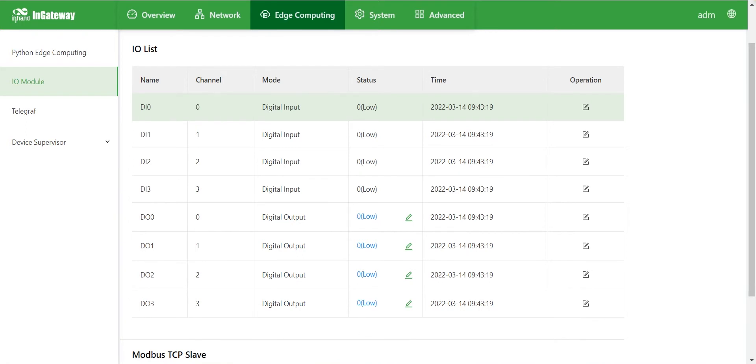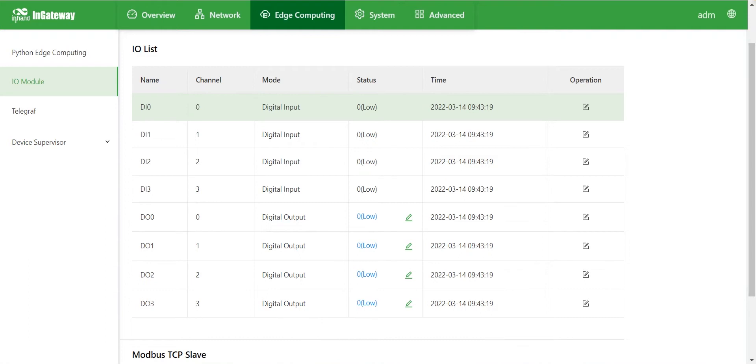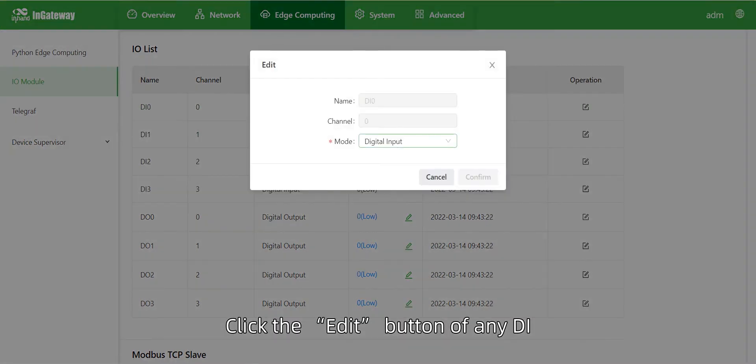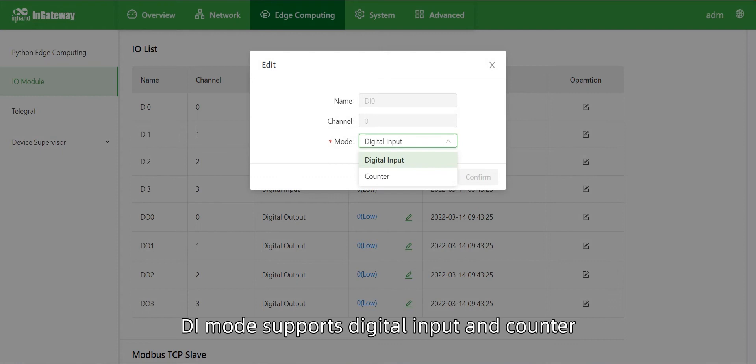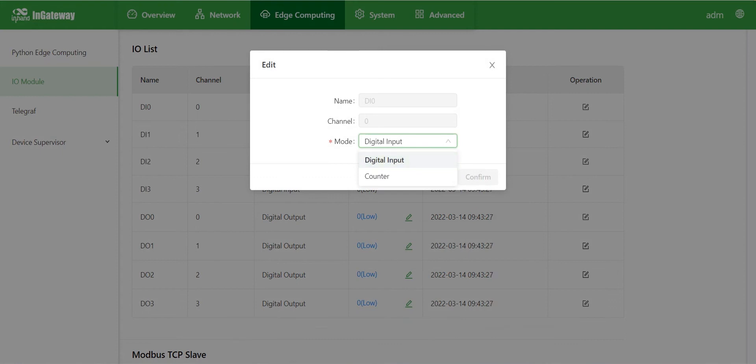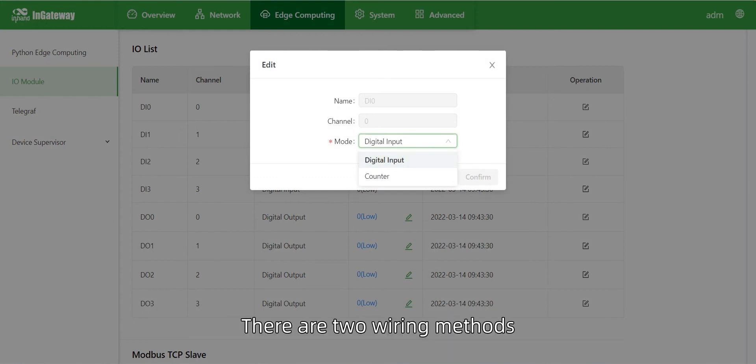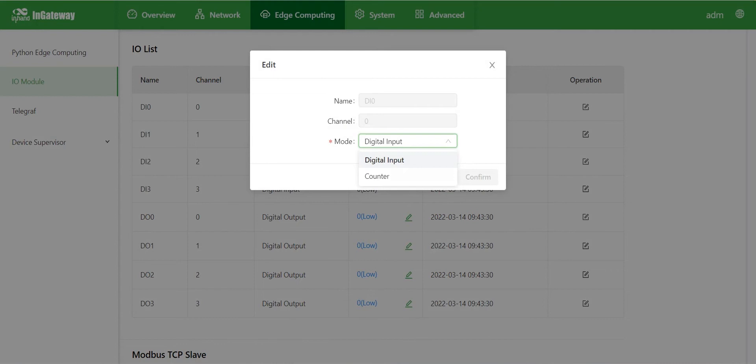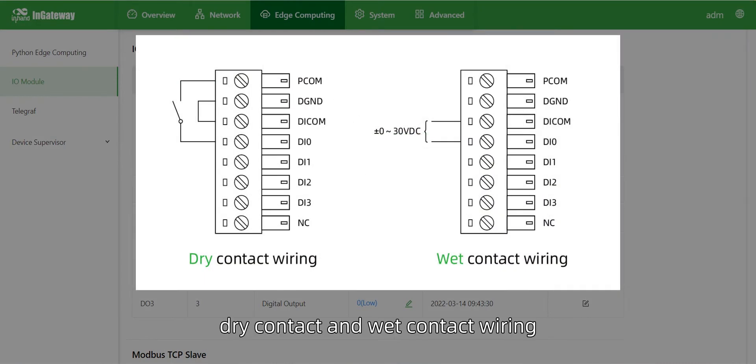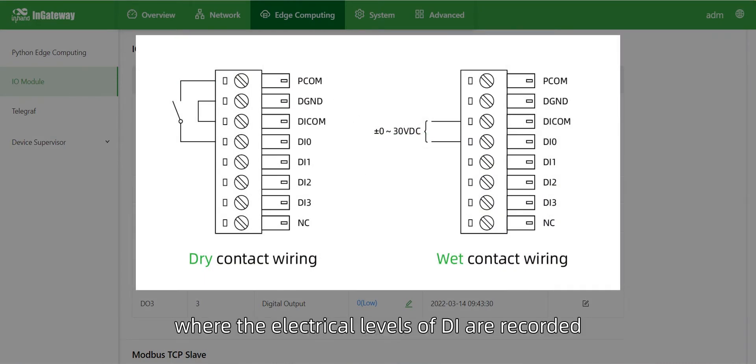First, let's show you how to configure D.I. Click the Edit button of any D.I. D.I. mode supports digital input and counter. In the mode of digital input, there are two wiring methods: dry contact and wet contact wiring, where the electrical levels of D.I. are recorded.